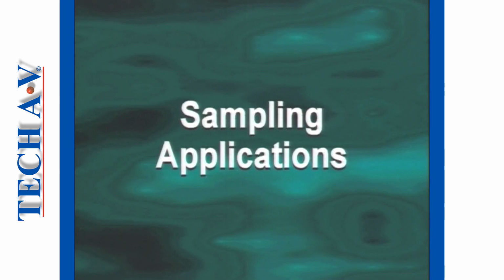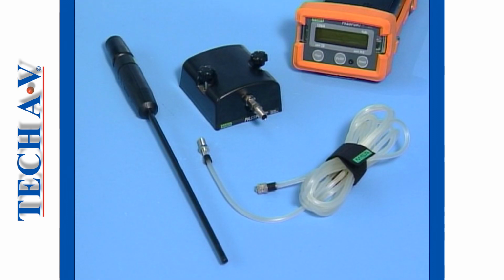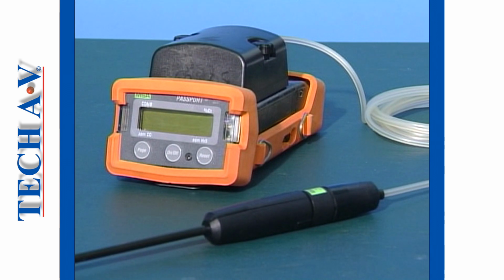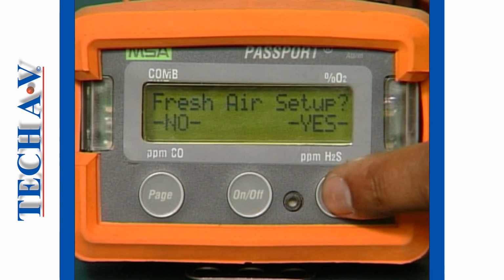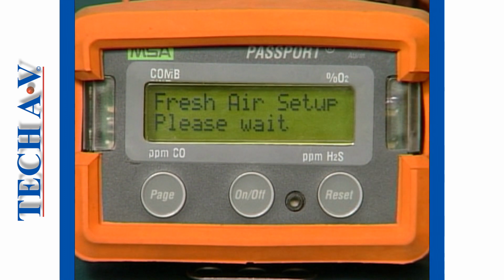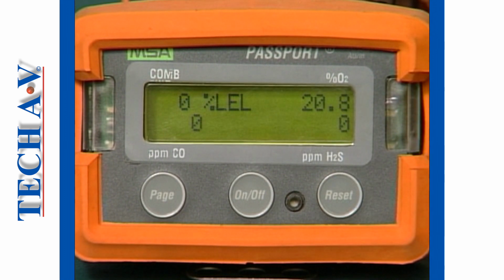Let us now consider the use of an instrument that has been configured as a sampling device. Our monitor has now been fitted with the automatic pump and the accompanying sampling line and probe. Next, we must check that the calibration is set and that the oxygen standard is reading 20.8%. This is done with the unit running in fresh air away from the area that we need to sample.